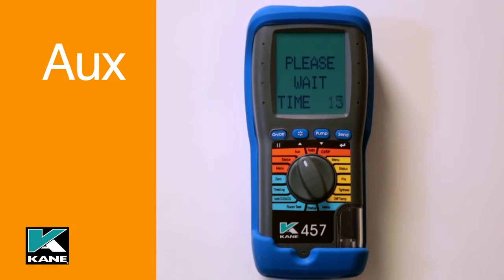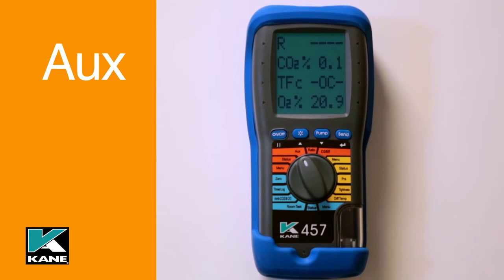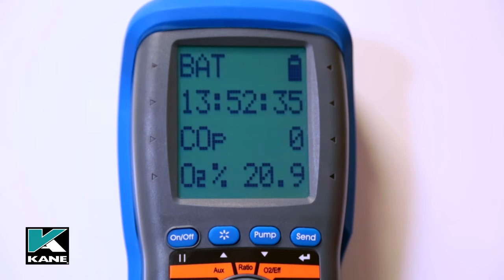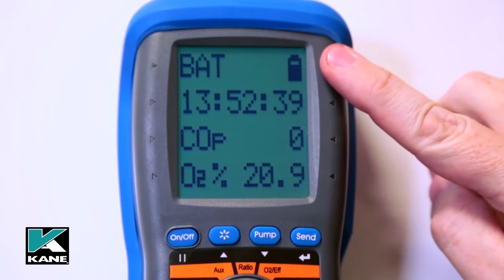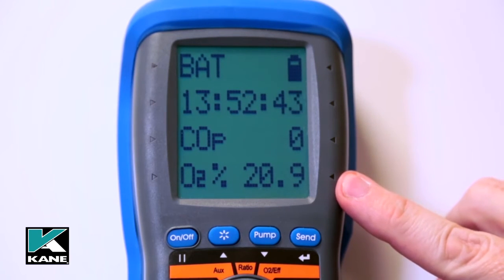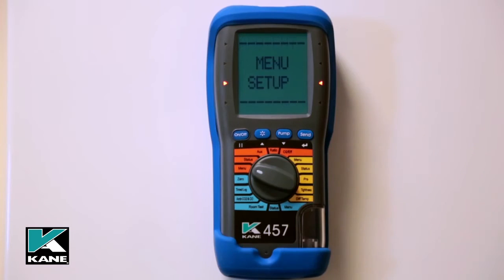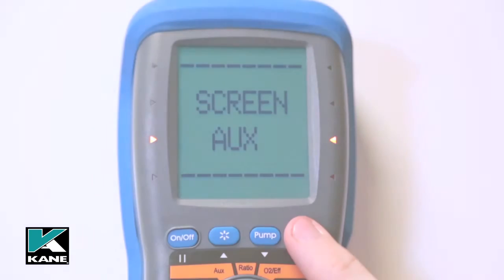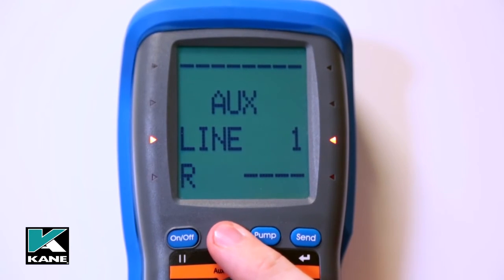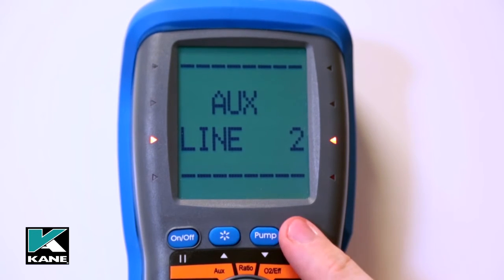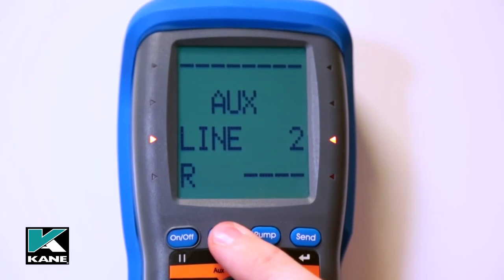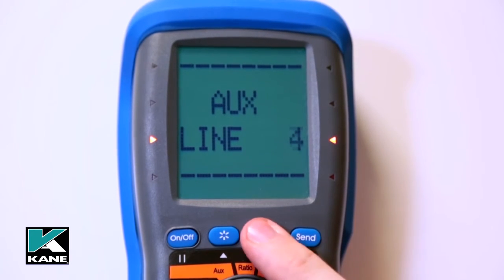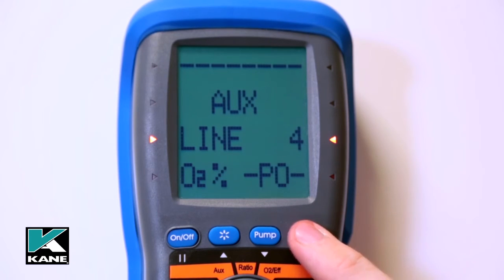The auxiliary screen, or AUX, allows you to customise a screen to suit your user-defined specific requirements, reducing setup time — for instance when commissioning an oil boiler. The parameters on lines 1, 2, 3, and 4 can be set independently. To customise the AUX display, select menu, screen, AUX. For each line use the up or down key to select the required parameter and press send to confirm. When all four lines are set, press send to save the AUX screen. They remain the AUX parameters until changed again by the user.